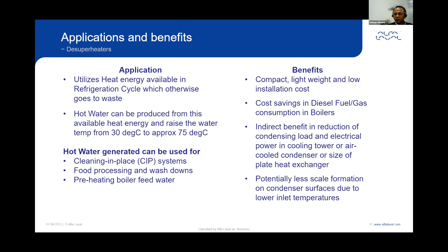These units offer several benefits. They are compact, efficient heat exchangers and have low installation cost compared to traditional shell and tube heat exchangers. They are a quarter of the size and weight of equivalent shell and tube units. Very low approach temperatures of between 1.5 to 2 degrees C can also be achieved. They also provide cost savings in diesel fuel and natural gas consumption in boilers, reduction in condensing load and power consumption in cooling tower or air-cooled condensers, or the size of the plate heat exchanger, and potentially less scale formation on condenser surfaces due to lower inlet temperatures.